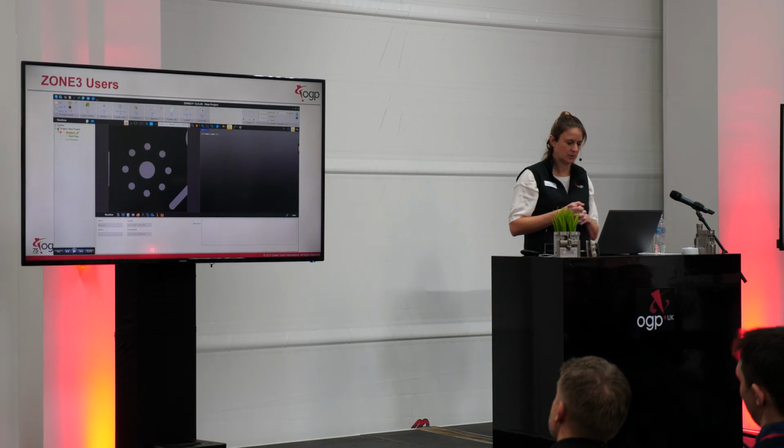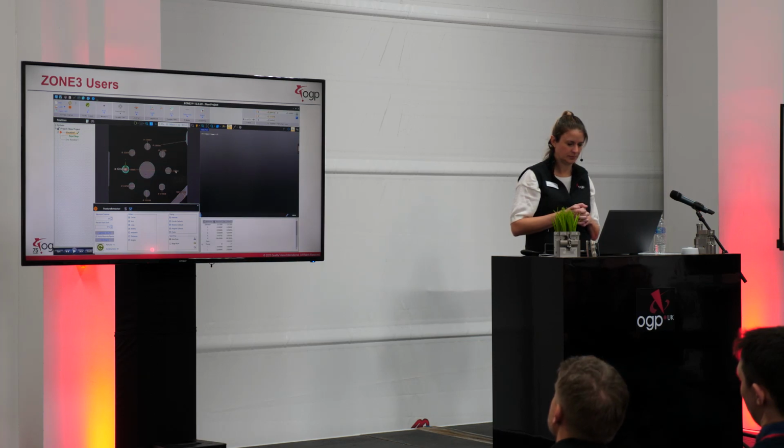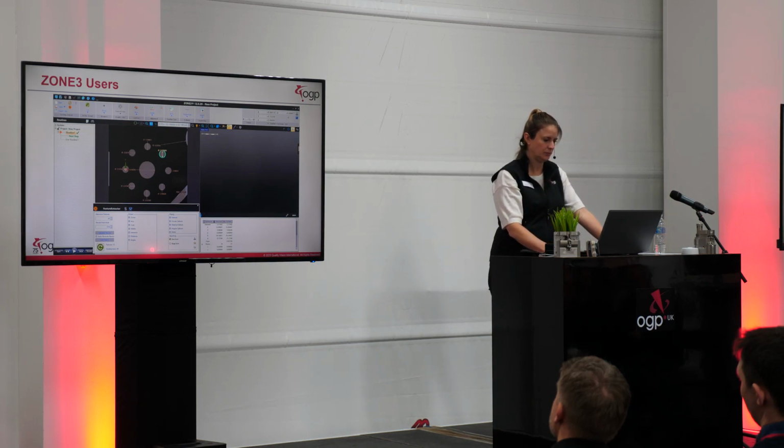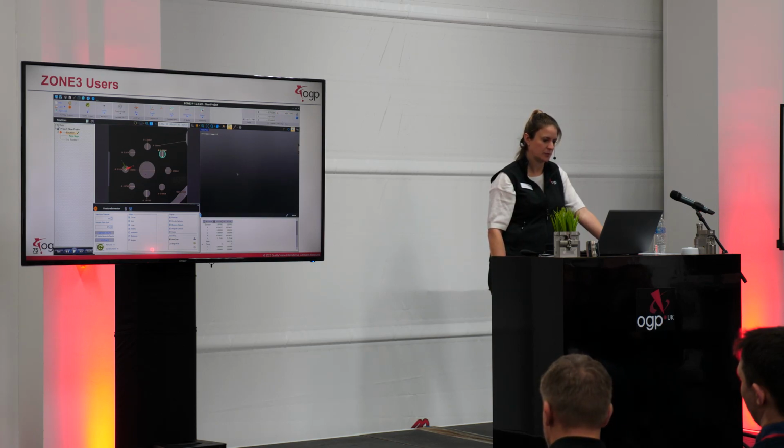To obtain position information from extracted features, the coordinate system can be aligned to an extracted feature. Simply click a feature and zero that out in the DRO. Now, when reporting additional features, the location is based on the origin, which is aligned to the extracted feature. Orientation of the origin can also be controlled through the DRO. This allows a coordinate system to be set up through multiple extracted features.